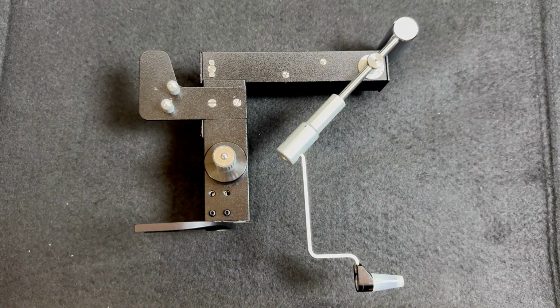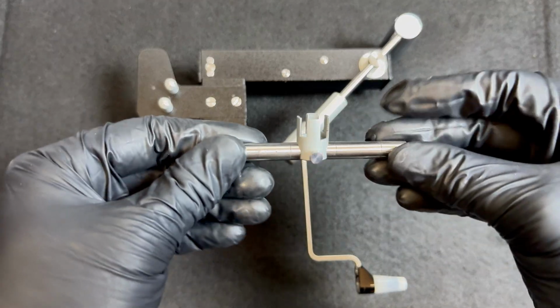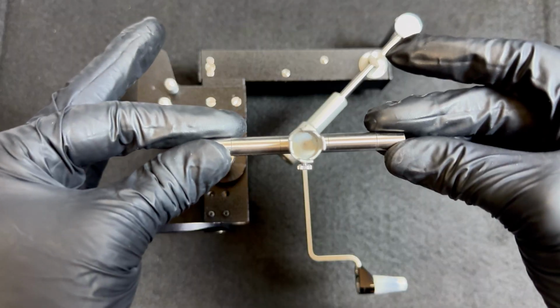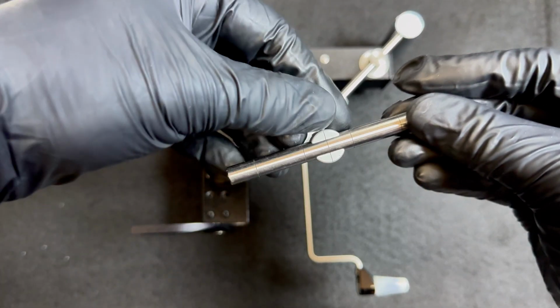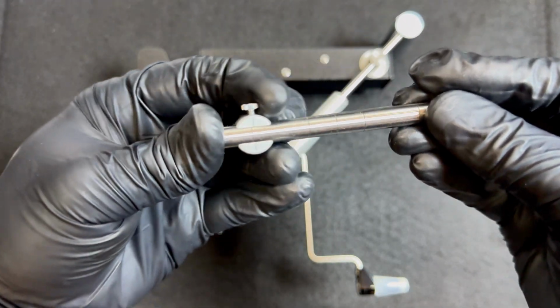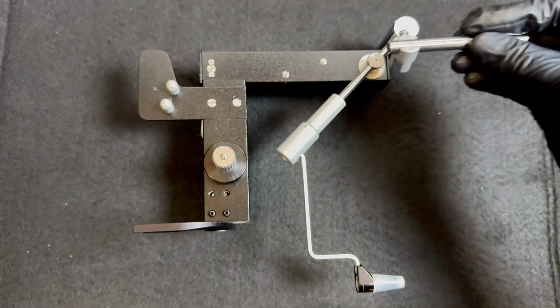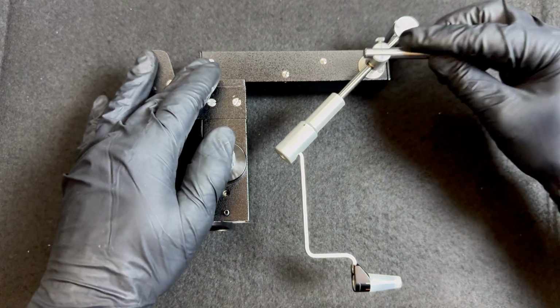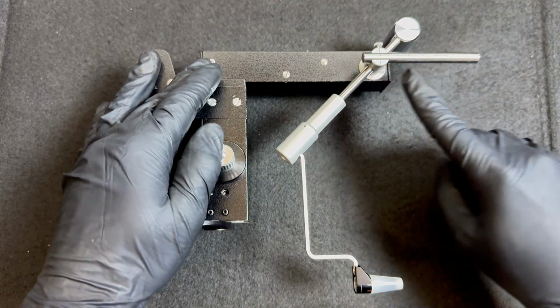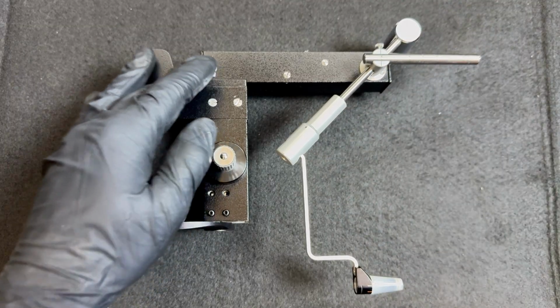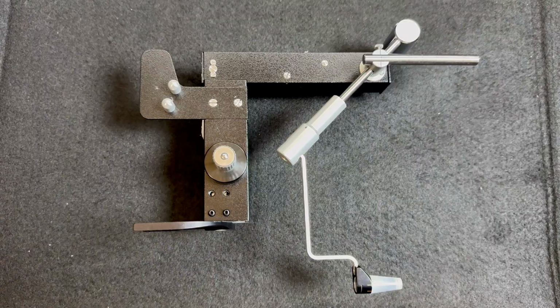On the 870 model tonometer, the calibration check procedure is nearly identical. Here, we are setting the adjustment weight to the 6th position. Fit the holder and weight over the tonometer axis. The key difference is that the longer end of the weight must be oriented toward the patient side.